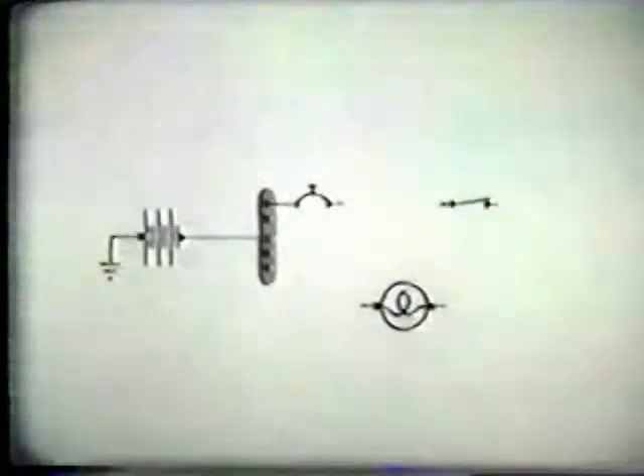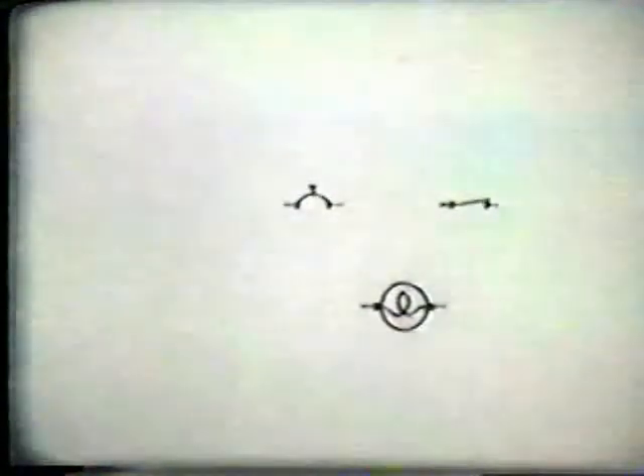A short will always make a circuit breaker pop or blow a fuse. There are rare cases when trouble occurs before the circuit breaker, but this will always cause many electrical units to be non-operative. The bulb did not light, and the circuit breaker remained in. We know we have an open. How do we locate the open? First, of course, we check the navigation light bulb. Odds are it is burned out, but we find the bulb is all right. The socket is clean and the bulb is well seated. We know that we have a circuit open somewhere between the bus bar and the ground of the light bulb socket.